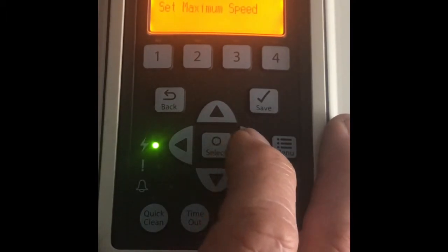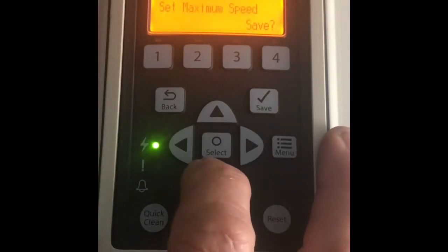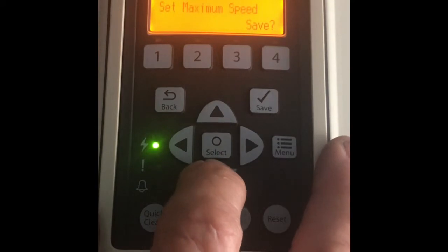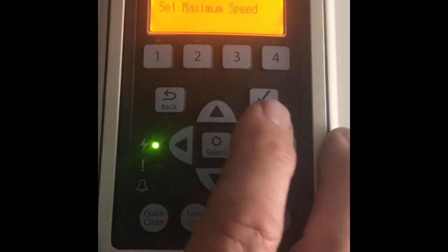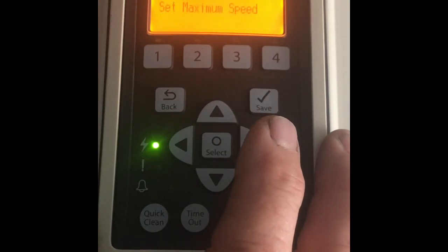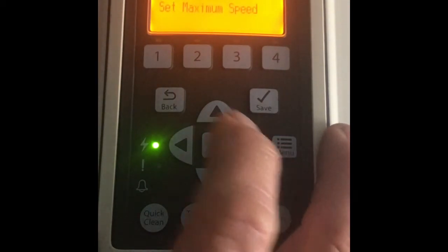So if you have 2-inch plumbing, we're going to select that. We're going to go over to the 3, make it a 2, go over to the 4, make it a 9, go over to the 5 and make it a 0. And we're going to hit save. So now we have the equivalent of about a 1.5 horse pump, if that's what you had. So if you had a 1 horsepower, then you would have to address that accordingly.